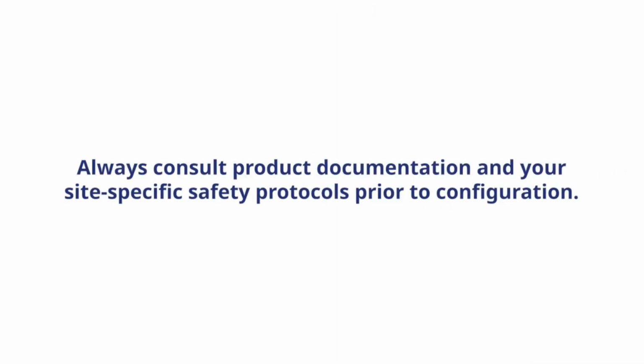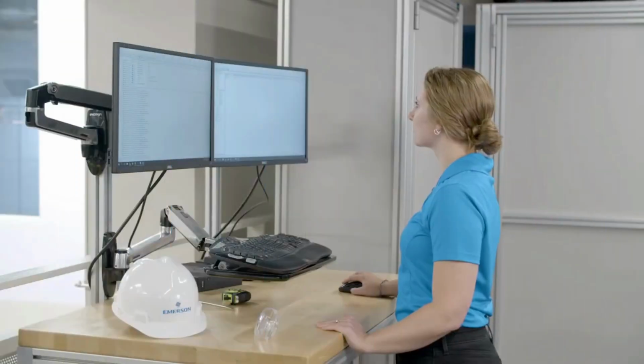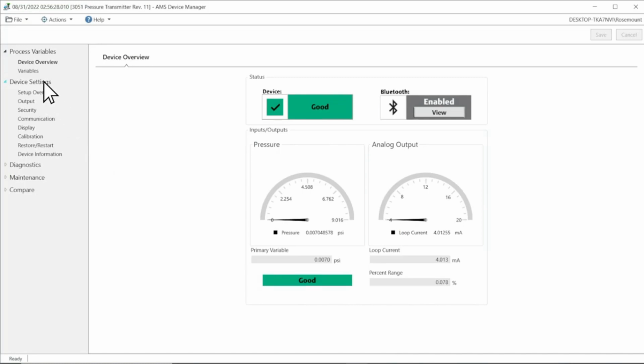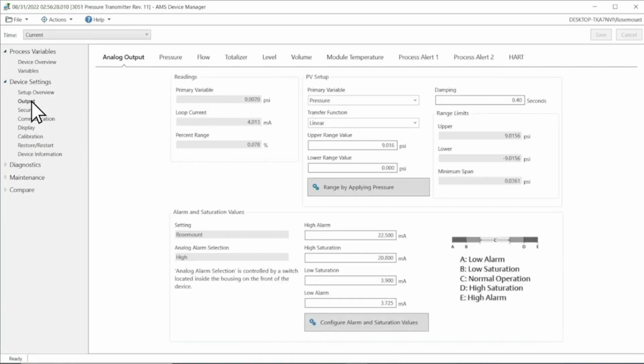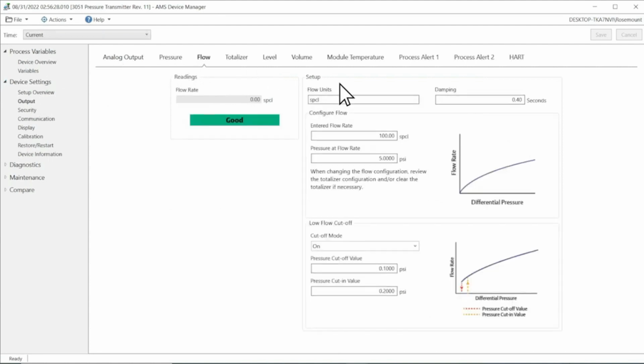Always consult product documentation and your site-specific safety protocols prior to configuration. Once connected to the transmitter, navigate to the Device Settings menu. Select Output, then Flow. First, enter your desired flow units. Next, set your reference flow rate in the entered flow rate box. Then, set the pressure value that is associated with the entered flow rate. This correlation will be maintained over the full flow range based on the square root relationship.